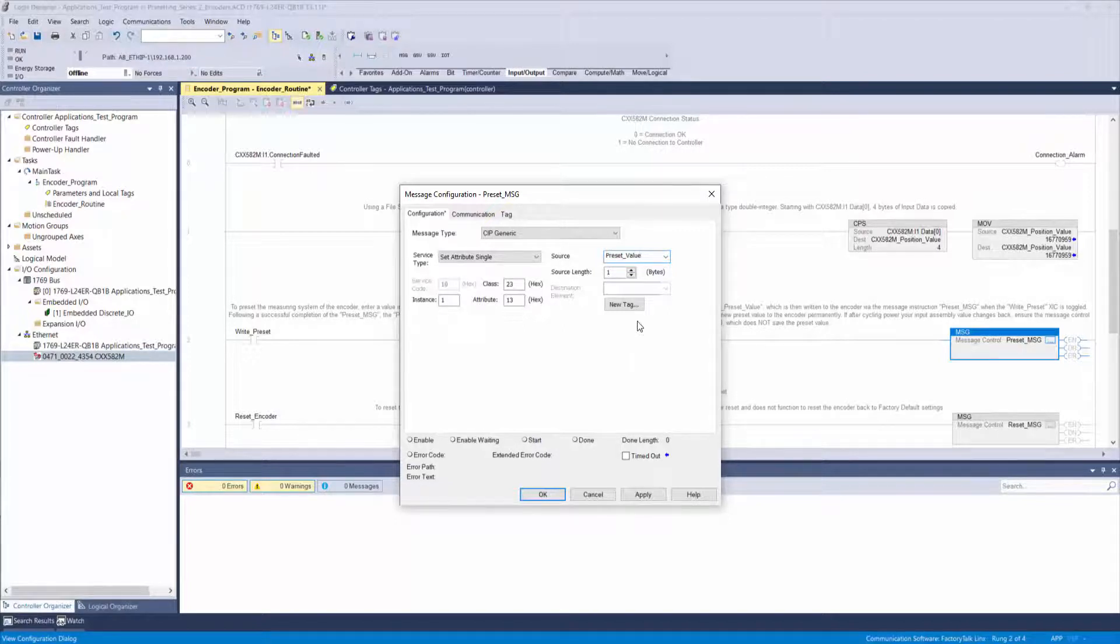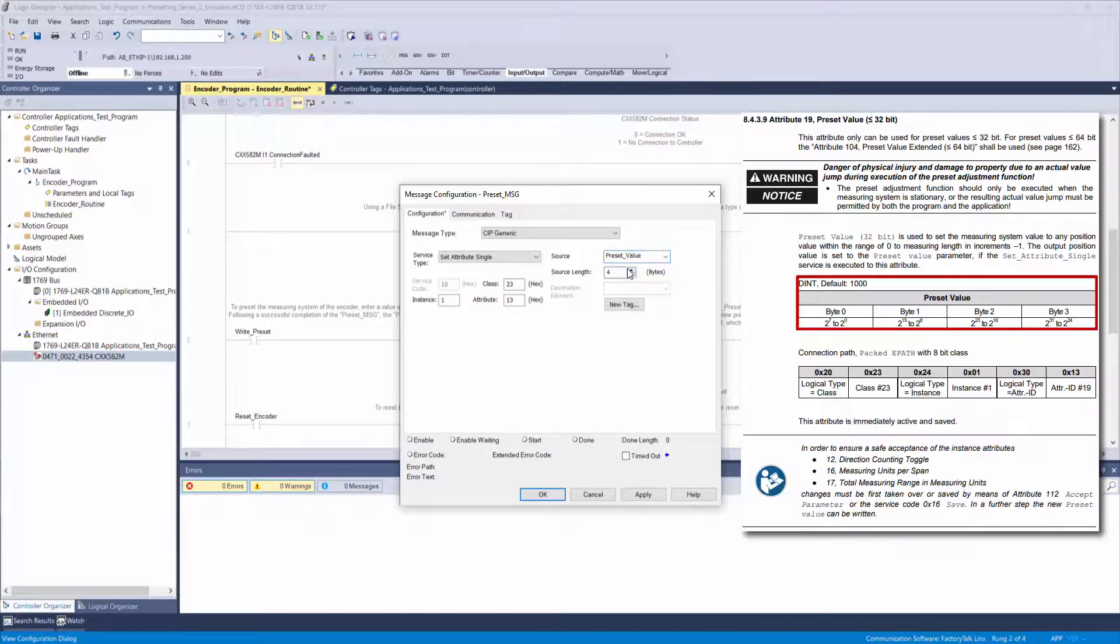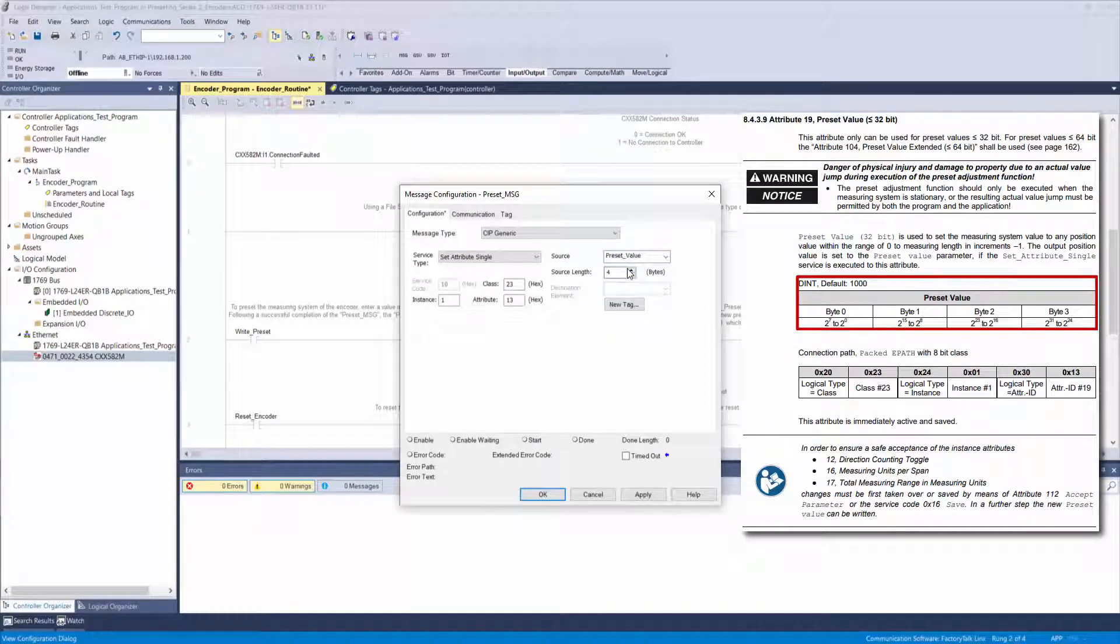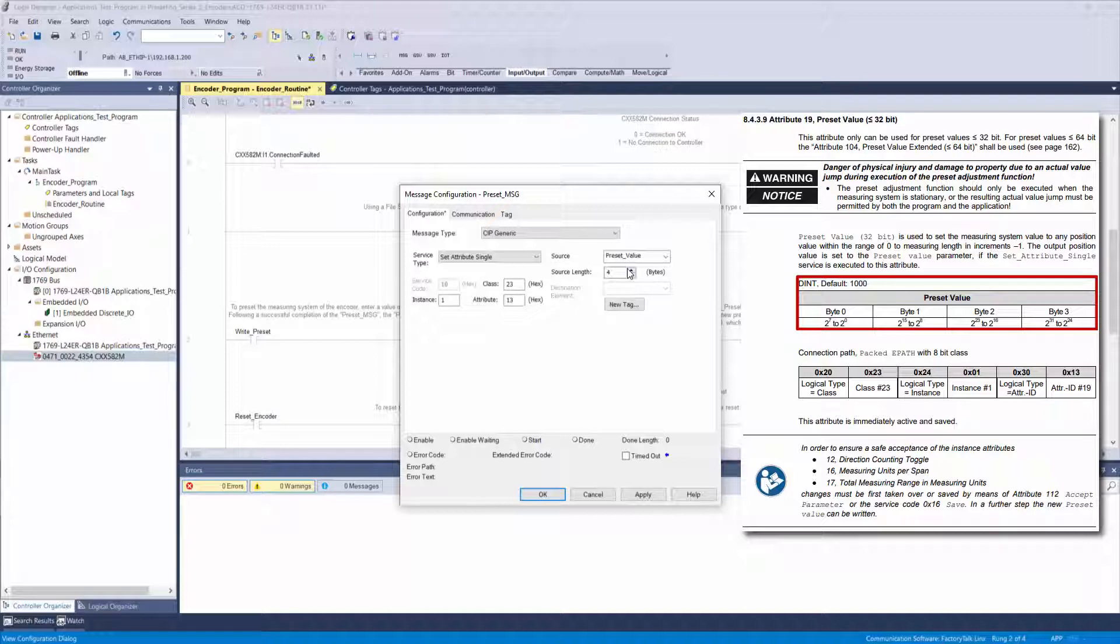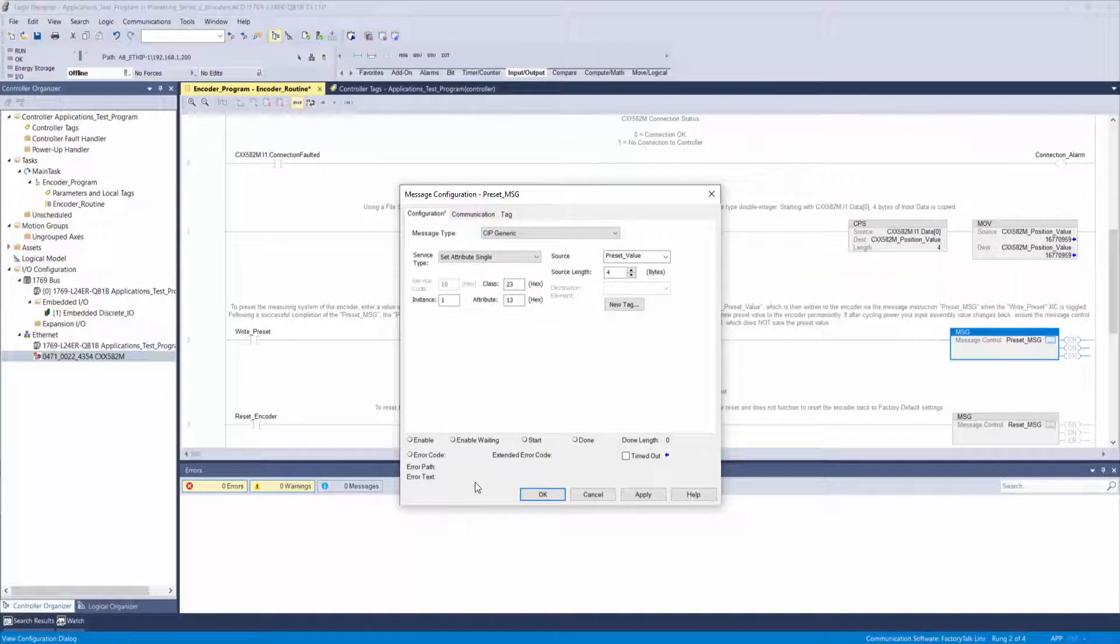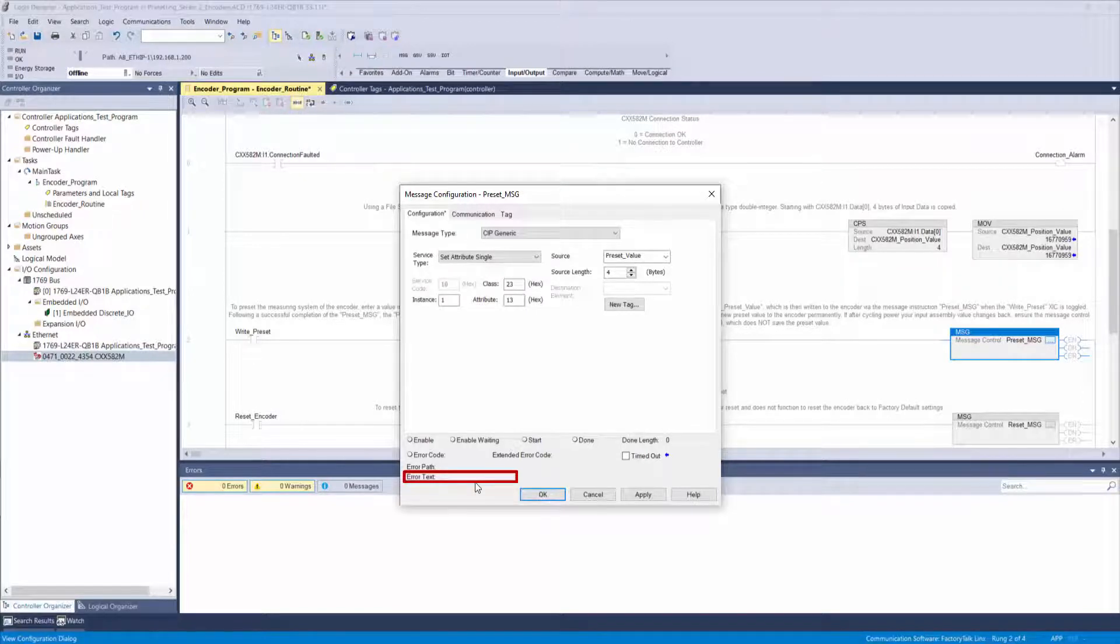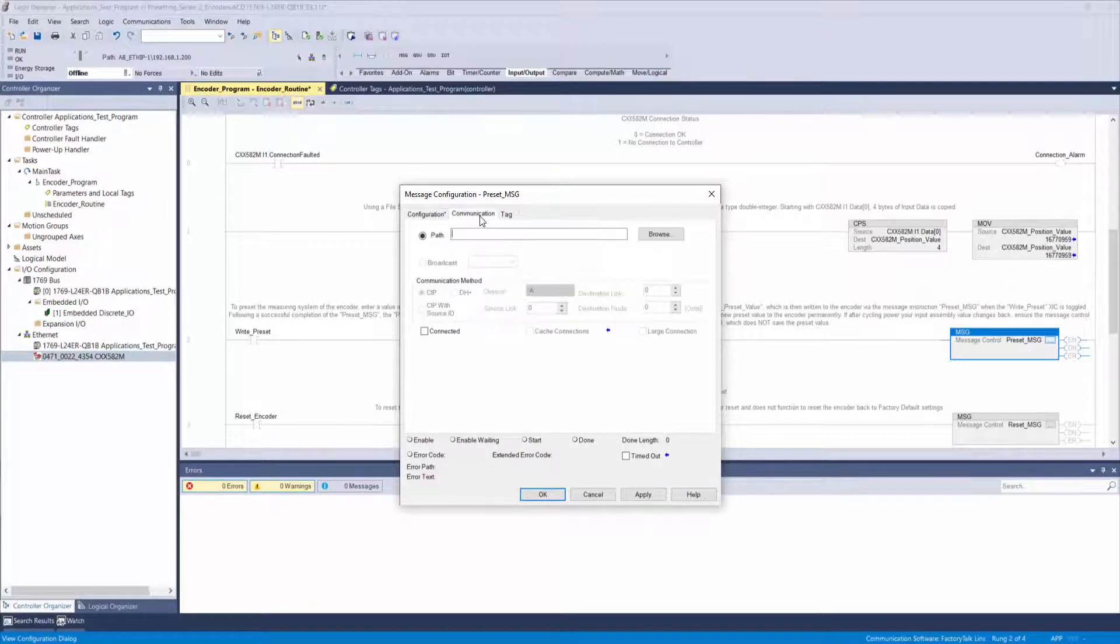Now select that tag as your source. Your source is the value that will be written to the encoder via this message instruction. We will define it shortly, but the manual indicates that the source length needs to be 4 bytes. If you do not set this correctly, the message instruction may error and you can look here for the error text. It will indicate whether the source length is too small or too large.